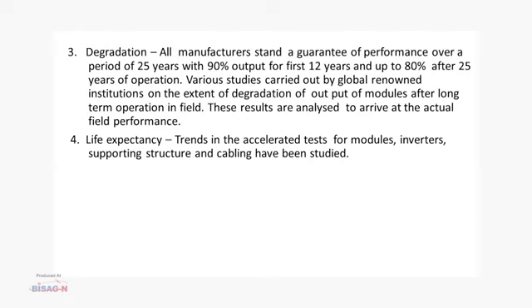Third one is degradation. All manufacturers extend a guarantee of performance over a period of 25 years with 90% output for first 12 years and up to 80% after 25 years of operation. Various studies have been carried out by globally renowned institutions on the extent of degradation of output of modules after long term operation in the field. These results are analyzed to arrive at the actual field performance. Next is life expectancy. Trends in the accelerated test for modules, inverters, supporting structure and cabling have been studied.